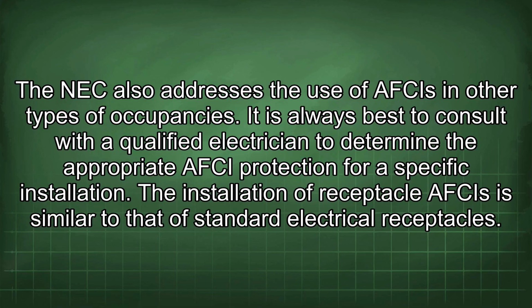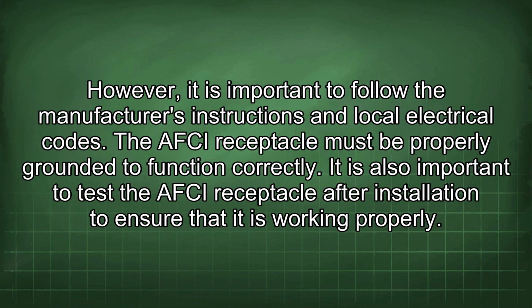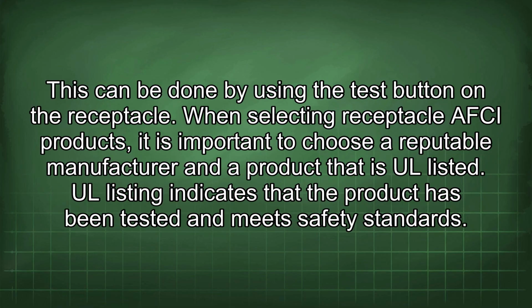The installation of receptacle AFCIs is similar to that of standard electrical receptacles. However, it is important to follow the manufacturer's instructions and local electrical codes. The AFCI receptacle must be properly grounded to function correctly. It is also important to test the AFCI receptacle after installation to ensure that it is working properly. This can be done by using the test button on the receptacle.